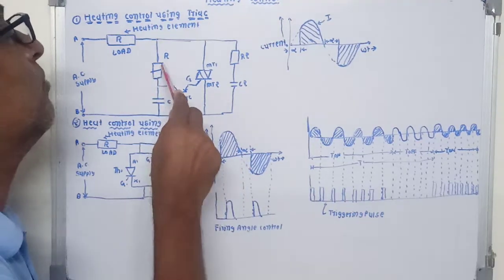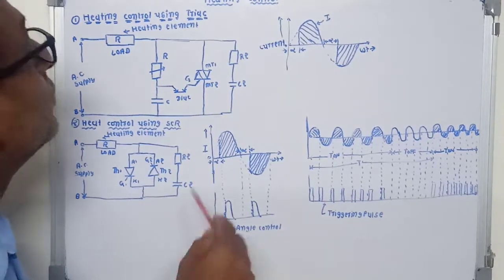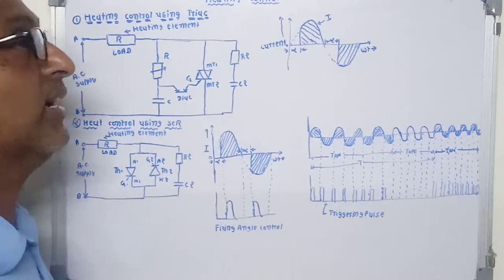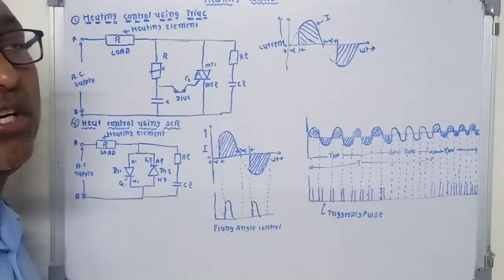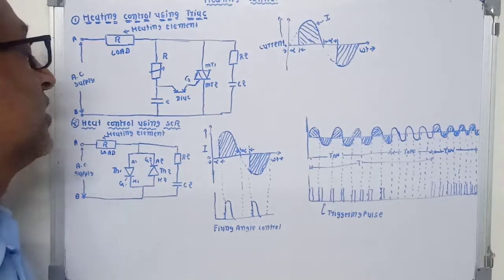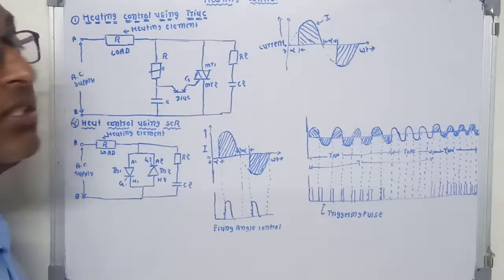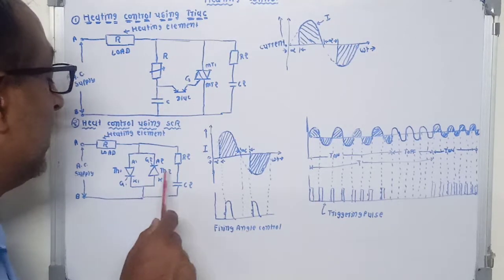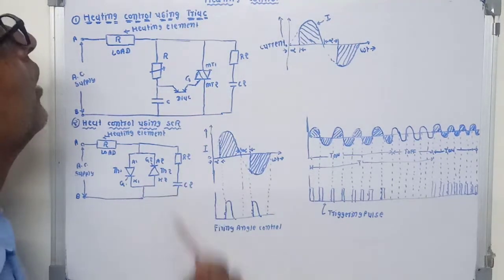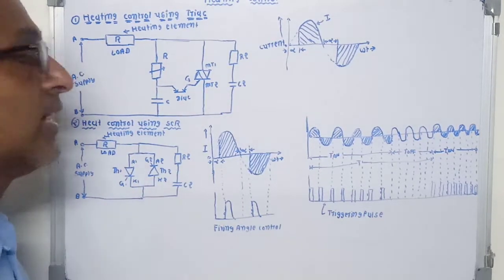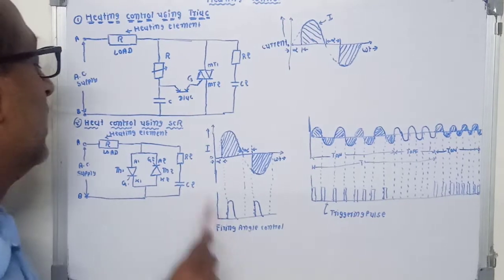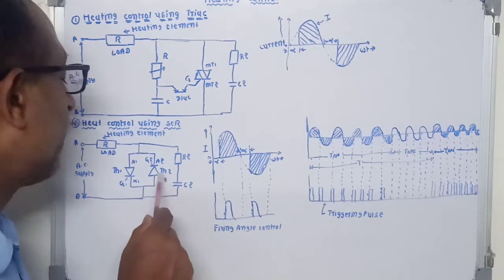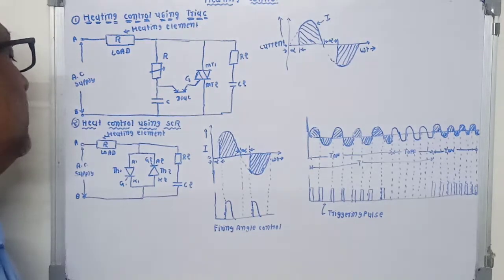The heat control can be achieved by adjusting this variable resistance R — this is most important. For heat control using SCR, the SCR is used for heating control of higher-capacity furnaces. As shown in the figure, since we use AC supply, two SCR thyristors — thyristor 1 and thyristor 2 — are used, connected in anti-parallel. R2 and C2 form a snubber circuit providing dv/dt protection to thyristor TH1 and thyristor TH2. R is the heating element.